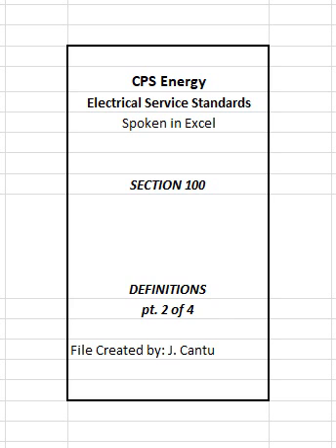Meter disconnect switch. A meter disconnect switch shall be rated not more than 600 volts and have a short circuit current rating equal to or greater than the available short circuit current. Meter disconnect switch shall be capable of interrupting the load served. The disconnect housing shall be metal and be grounded and bonded in accordance with applicable codes.